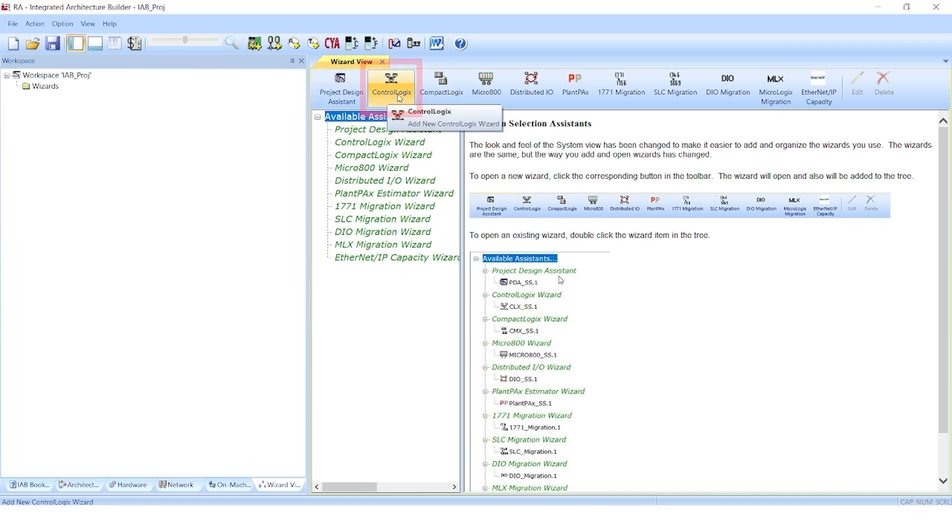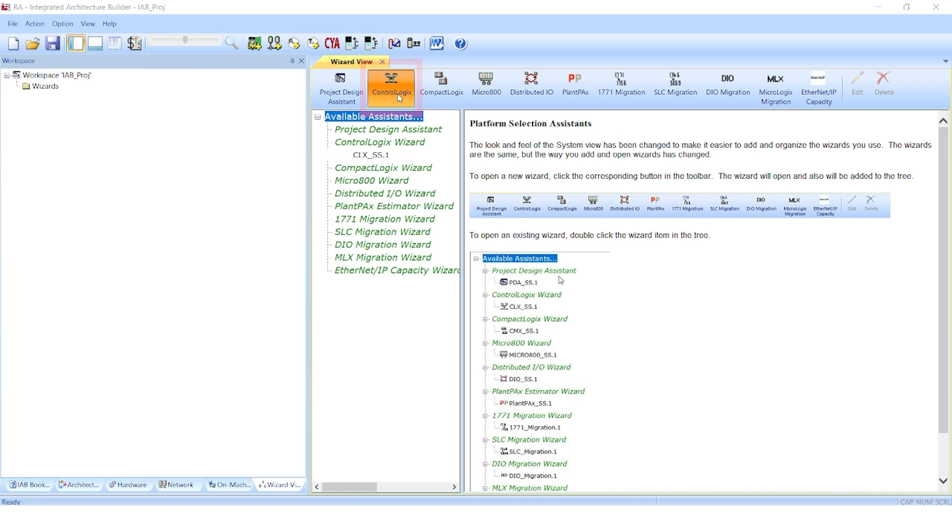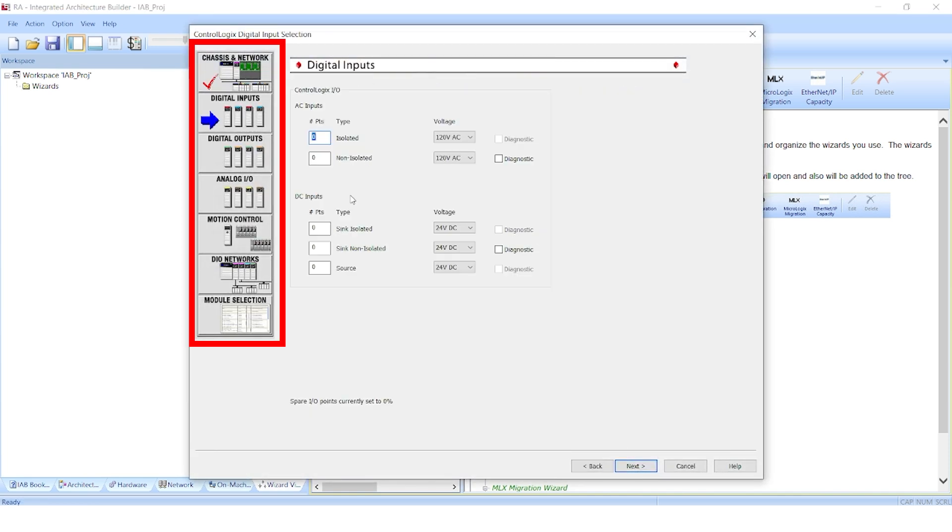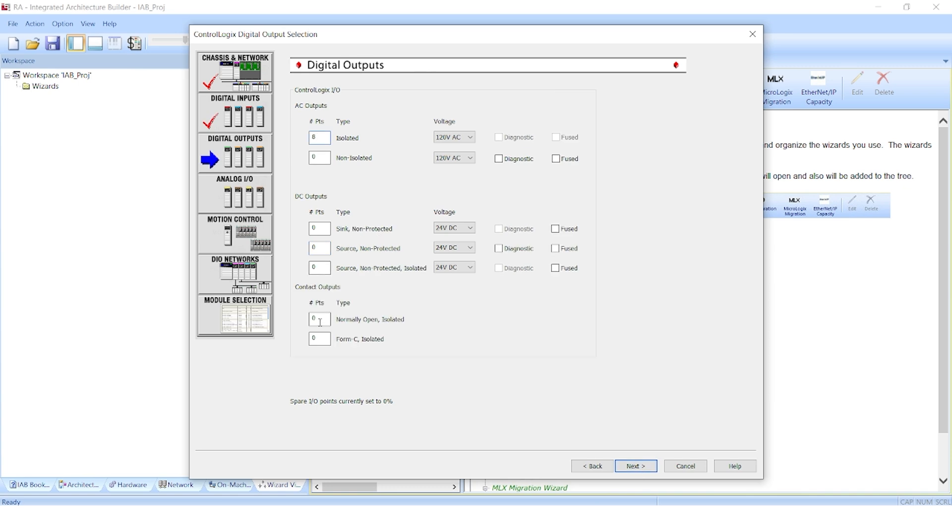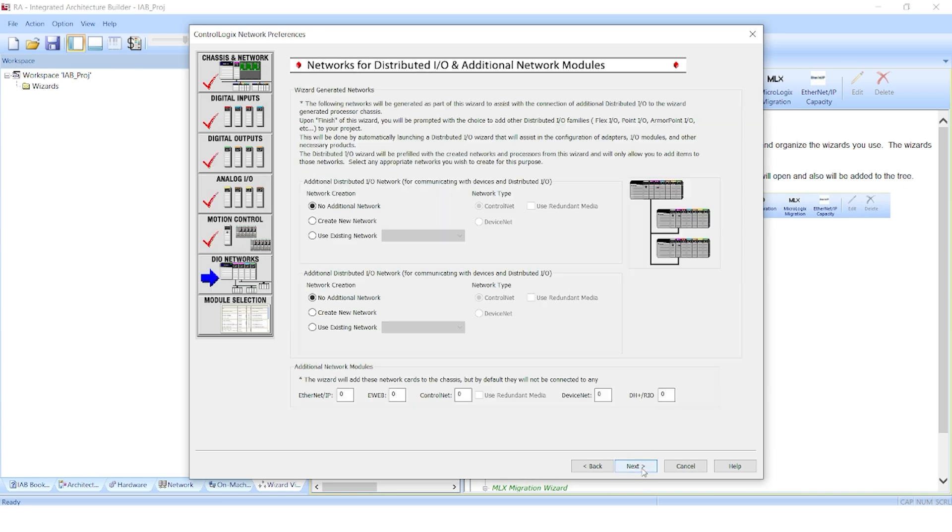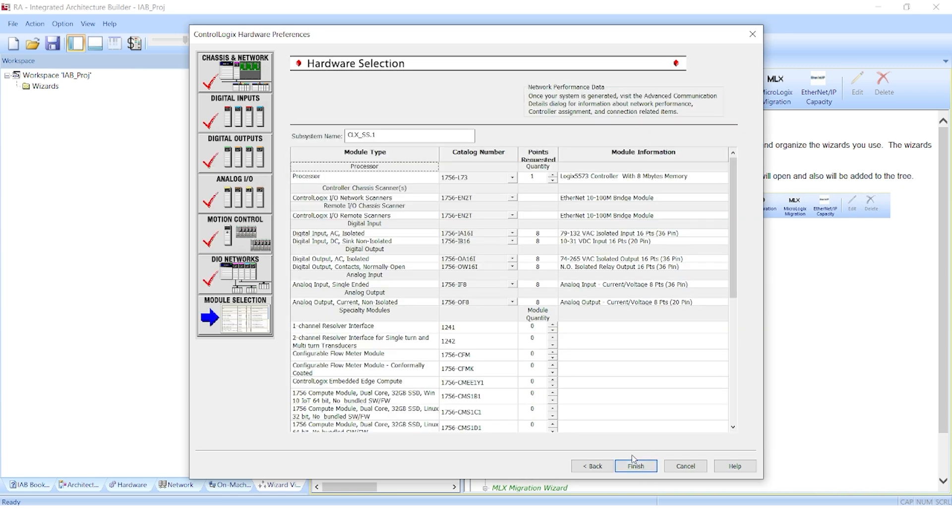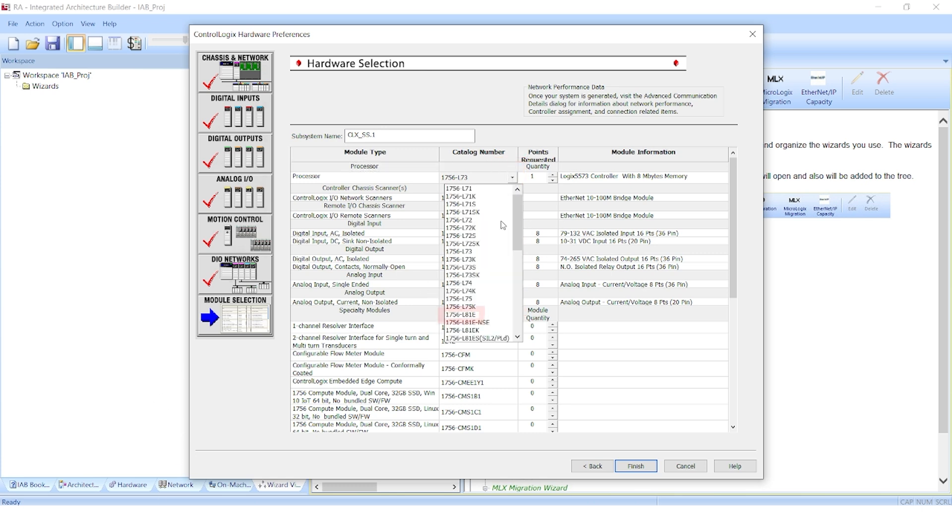In our example, we're going to build a ControlLogix system. In the wizard, it's going to step us through a series of windows to define our preferences for the chassis and network and then populate the various I/O options. On the last page of the wizard, it summarizes the data we have entered and provides a default listing of suggested I/O modules. You also have the option to change modules. In this case, we'll change the controller to an L81E. Once any changes are done, we select finish and generate the system.